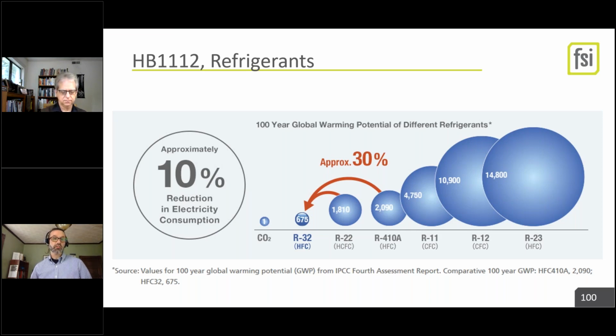CO2 has a global warming potential of 1, and everything's been indexed to CO2. R410A, that's your 2000s refrigerant replacing R22. Even R32 is much worse than CO2. But CO2 must run at very, very high pressure for it to work, and that has a cost impact because we need thicker coils, more robust compressors, higher pressure throughout.